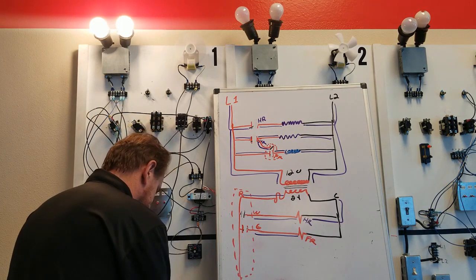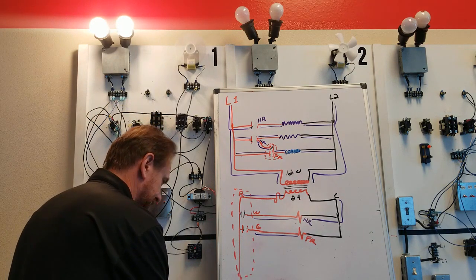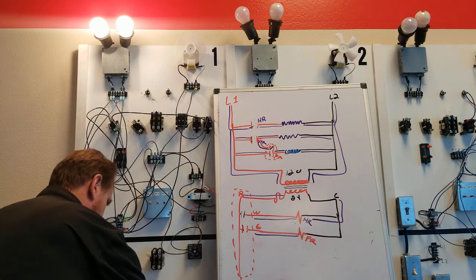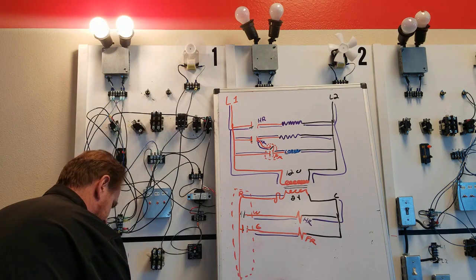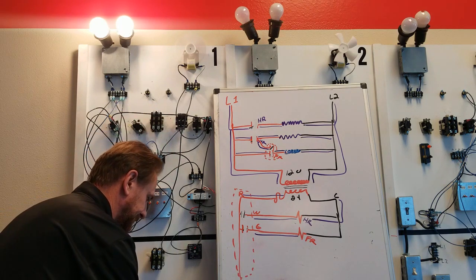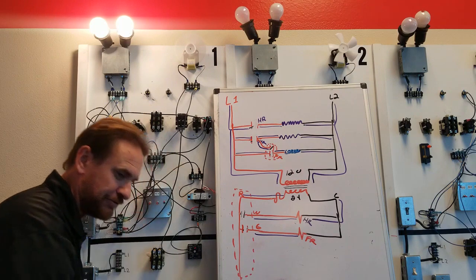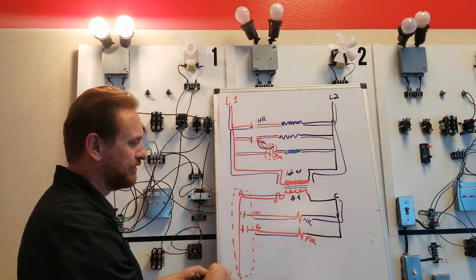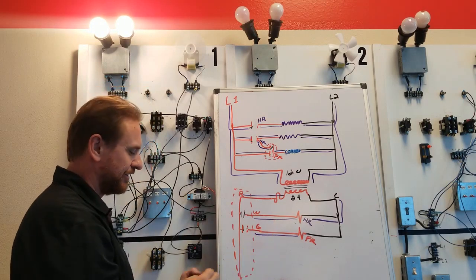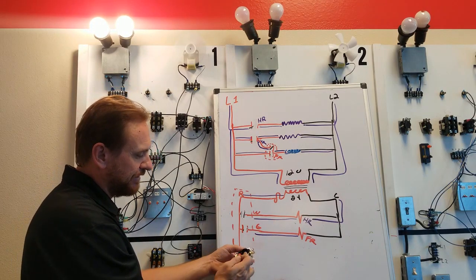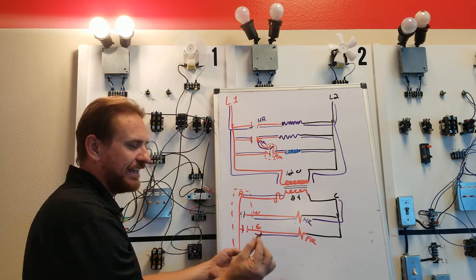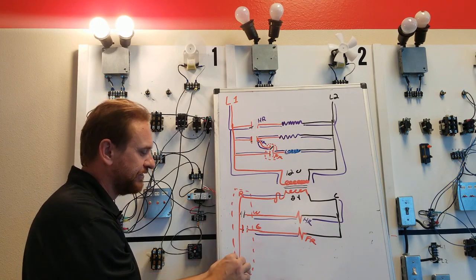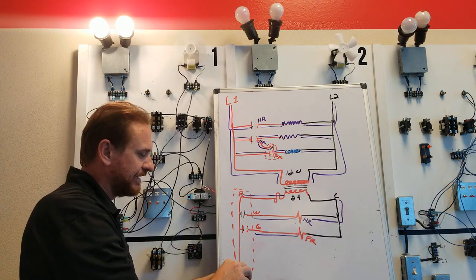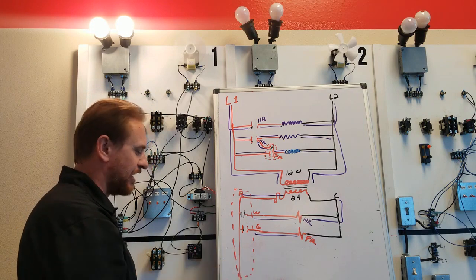The bimetal is just a piece of curved metal, which I seem to have lost. I must have dropped it. So there's a bimetal, which is a curved piece of metal, and this is a heater. The 24 volts comes in, doesn't go anywhere at the other side. It has to go first through this. This is the resistive element. So when we put these together, it goes through and it starts getting hot.